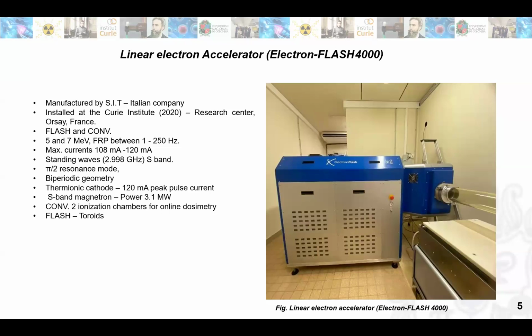Electron generation is achieved through a thermionic cathode delivering up to 120 milliamperes with a pulse width between 0.5 and 4 microseconds, at 3.1 megawatts. An S-band magnetron powers the system, protected by a circulator to prevent reflections.